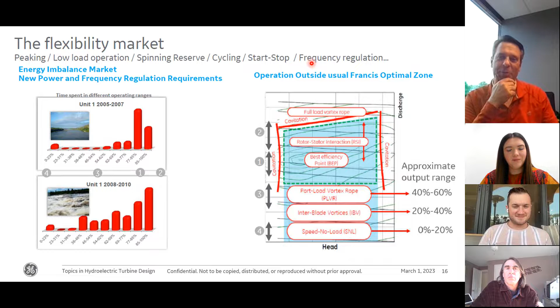One of the things we run into as equipment manufacturers when designing this is there are a lot of nasty things that happen at lower loads. So we have to design for that and take care of items that could really wreck a turbine if operated there for a long period of time. That's some of what we take into consideration in the flexibility market. This is what everybody's seeing now: peaking, low load, spinning reserve, cycling, starts and stops, frequency and regulation. It's only going to increase as we sell more turbines, and it's going to be more of a challenge for us. But hydro to the rescue.